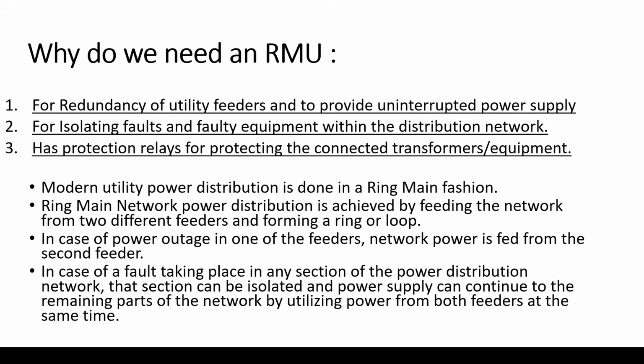How is this? This happens since you are able to connect all the loads in a ring fashion. Therefore, for each load, or let's say each transformer combination, you have two feeders coming. The purpose of the ring is that in the case of failure of one of the cables or feeders, you can feed the power through the other feeder. Plus also, as you will see in the coming slides, whenever any fault happens in any part of the network, you would be able to isolate that fault by changing the breaker configuration or by opening a certain part of the network, in order to ensure continuous power. Therefore, you are providing redundant power for all your projects or all your loads.